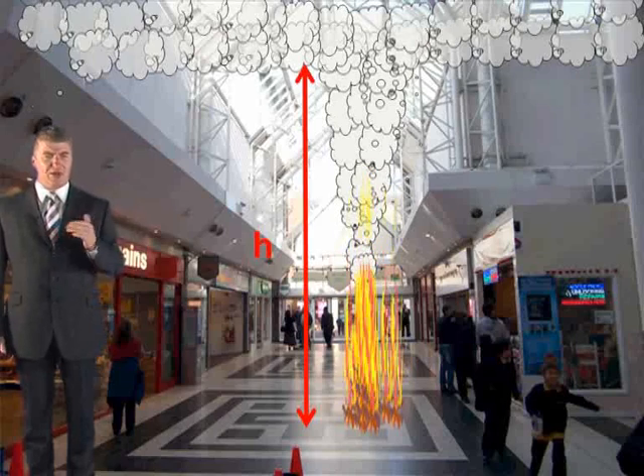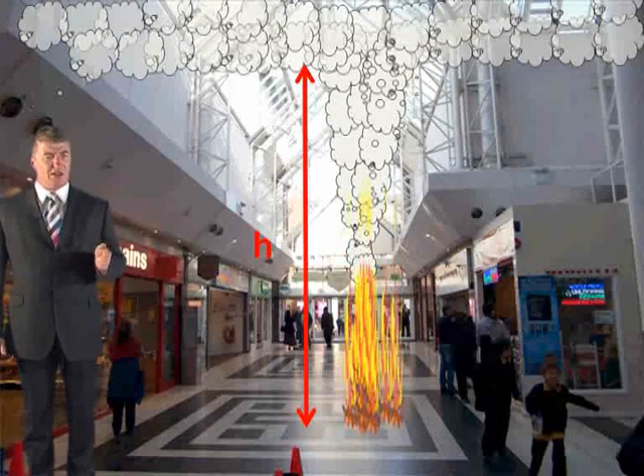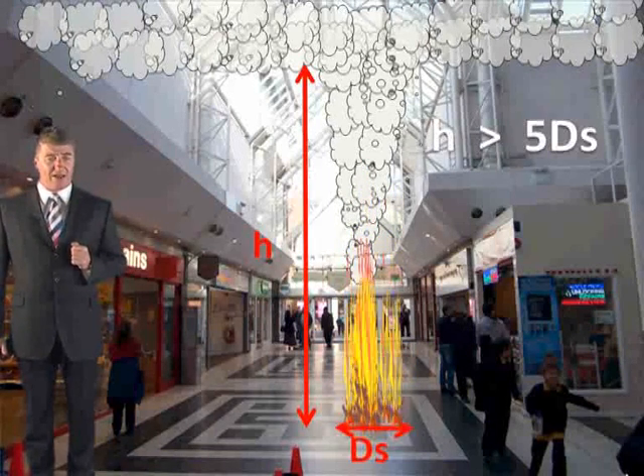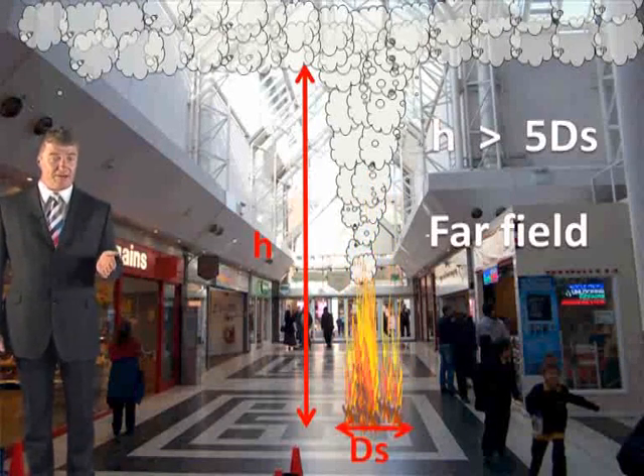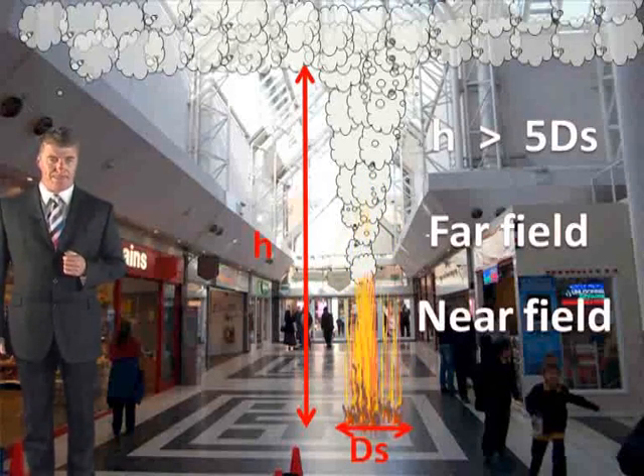First, we need to determine whether it's a near field or a far field model. The rule is that if the clear layer height is greater than the longest dimension of the source times 5, then it's a far field model. If not, it's a near field model.